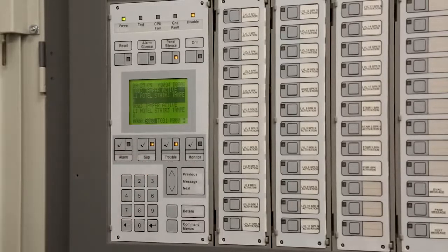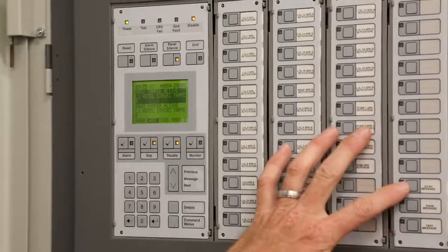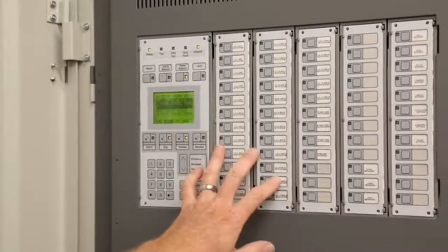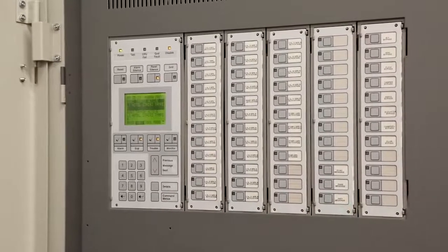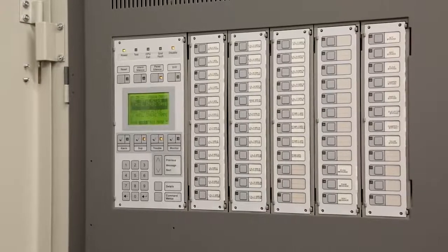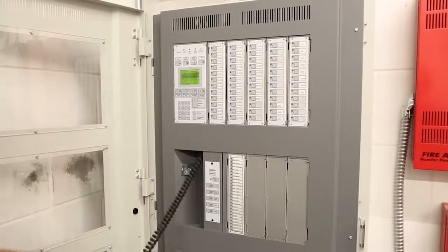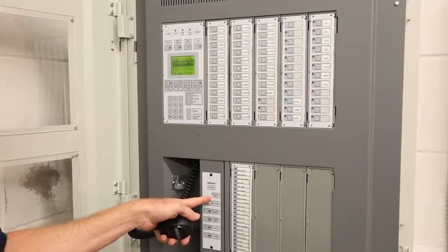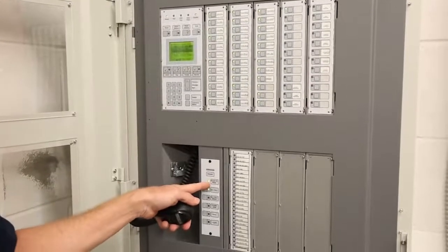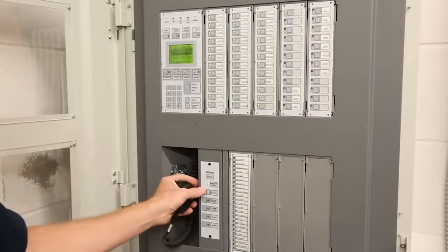I guess if we wanted to do an announcement, we can select the button here. You can hit page message and select what floor you want to go to. Or we have a test message for when doing testing or evac. Or if you want to talk to everybody on every floor, basically hit all call right here, key the mic, wait till that's picked. You notice all these lights are lighting up, everything's picked right now. Test 1, 2, 3, so it's going through the whole place. It doesn't set an alarm first? No.